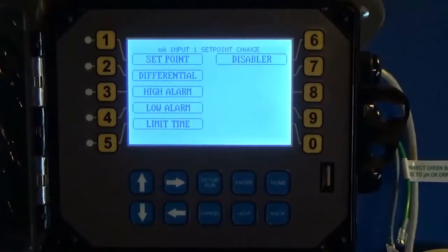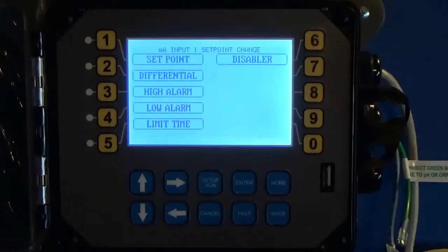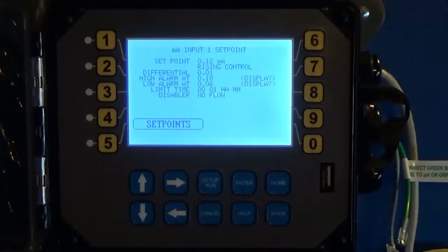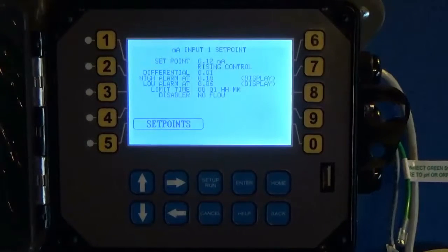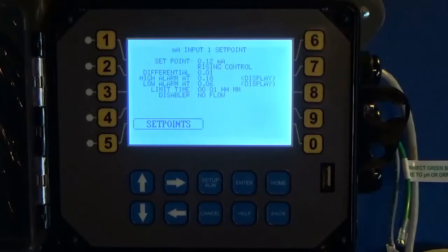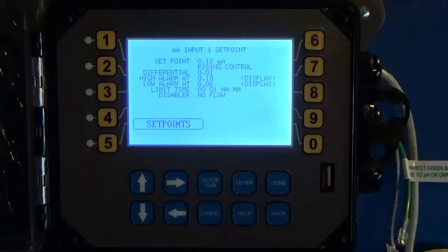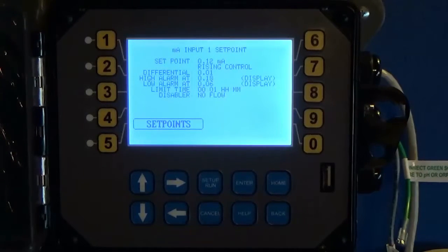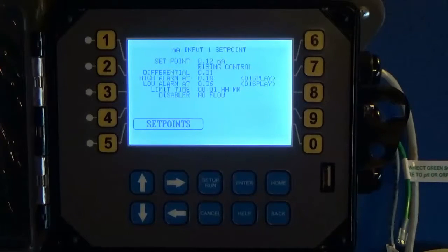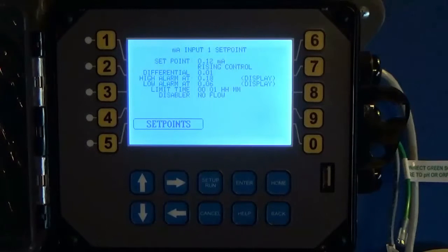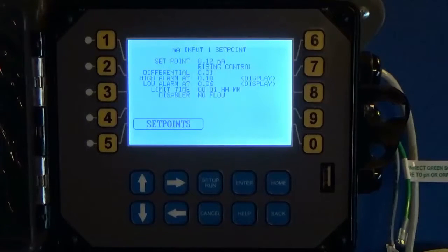I want to disable that feed based on no flow because I don't want to feed chemical or whatever I'm doing if there's no flow in the system. You don't have to select the disabler, but this is important to know. If you hook up say a fluorometer and you're feeding chemical based off of it, if you don't go in and tell it to shut off when there's no flow it won't. It will continue running.